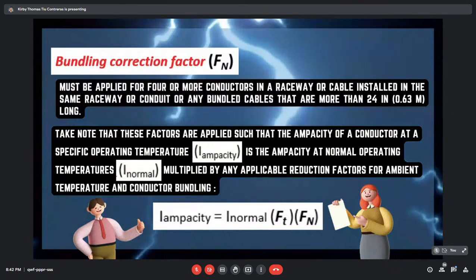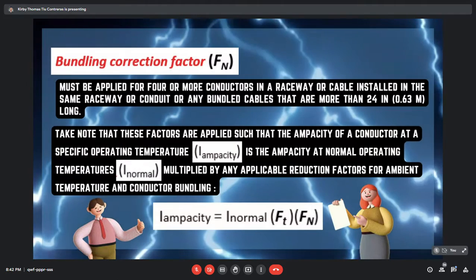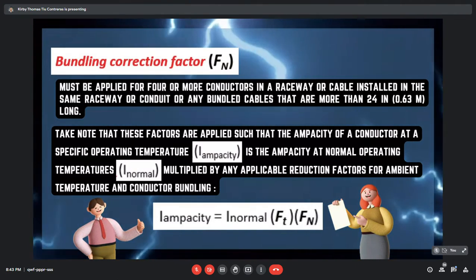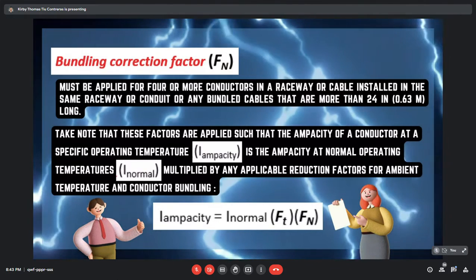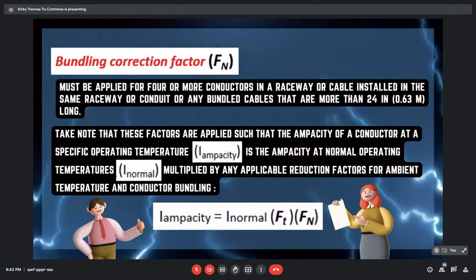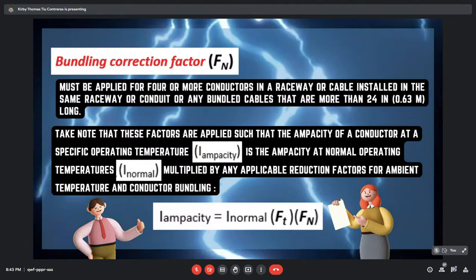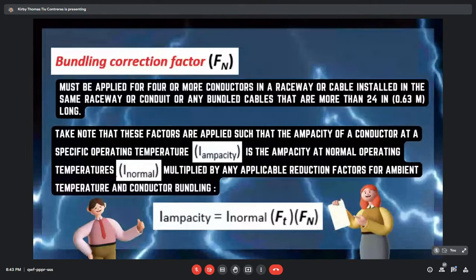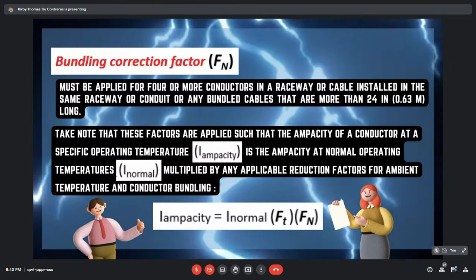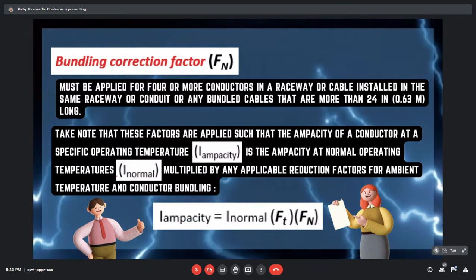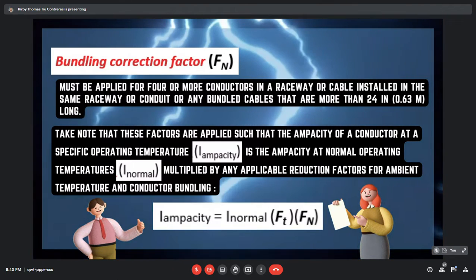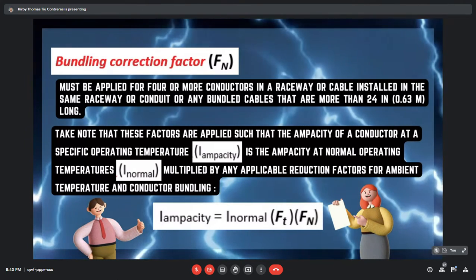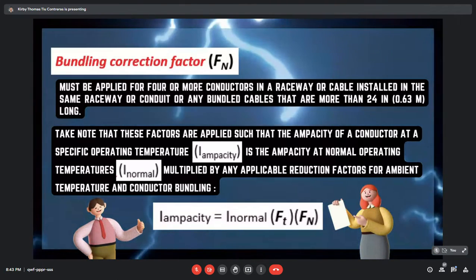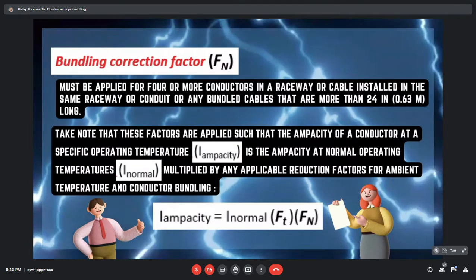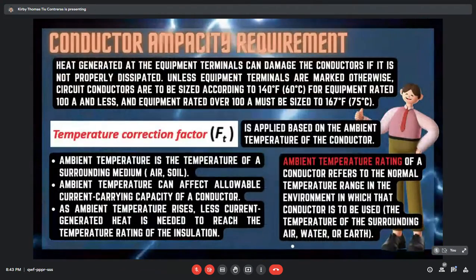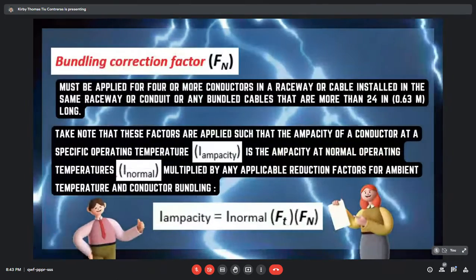The bundling correction factor. It must be applied for 4 or more conductors in a raceway or cable installed in the same raceway or conduit, or any bundled cables that are more than 24 inches or 0.61 meters long. So take note that these factors are applied such that the ampacity of a conductor at a specific operating temperature is the ampacity at normal operating temperatures multiplied by any applicable reduction factors for ambient temperature and conductor bundling. So mathematically, ingani ang pagka-express niya: I ampacity, or the ampacity of the conductor at a specific operating temperature, is equal to the I normal, or the normal operating temperature ampacity, multiplied by the FT, or katong temperature correction factor, multiplied by FN, or the bundling correction factor.